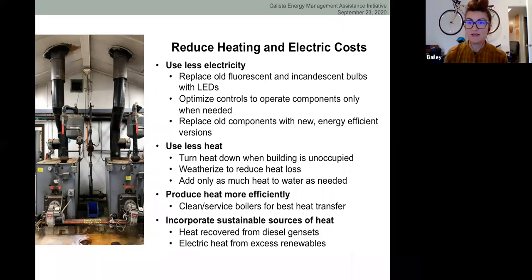water as needed. So engineers would generally agree that maintaining the water in the range of 36 to 40 degrees is enough to prevent it from freezing in the lines. But sometimes we'll see that water is being heated to 55 or 60 degrees, and that may protect it from freezing, but that's more heat than necessary, and that's burning a lot of fuel that doesn't really need to be burned. So just finding that sweet spot for what temperatures and how controls are set can help us to minimize the amount of heat that we're using in those facilities.